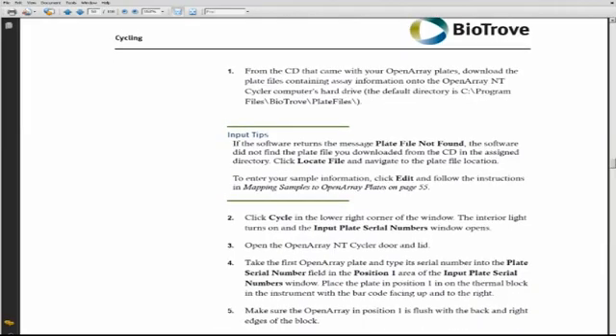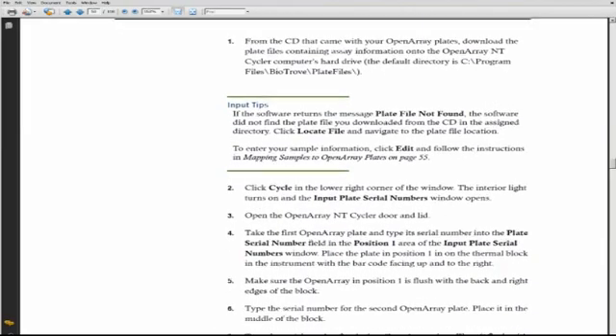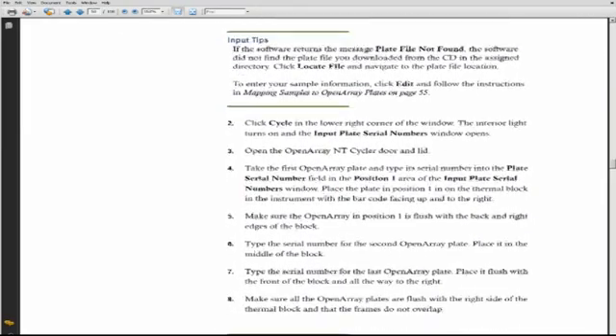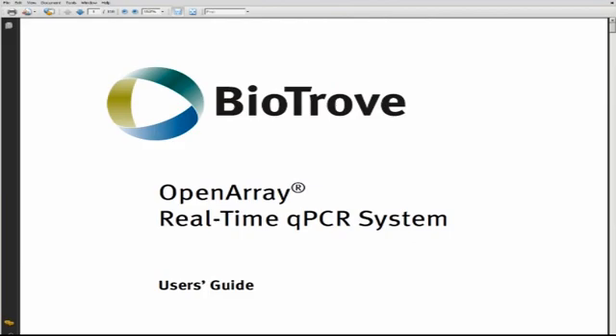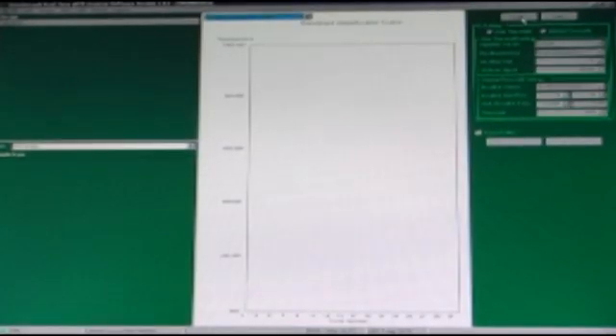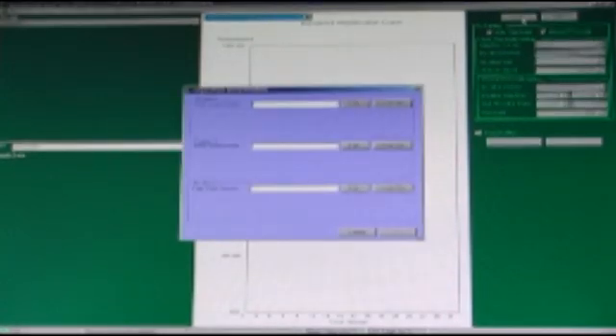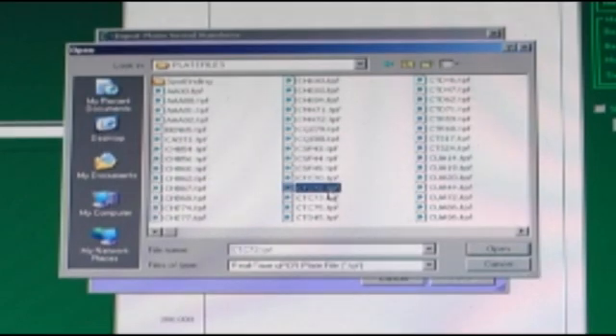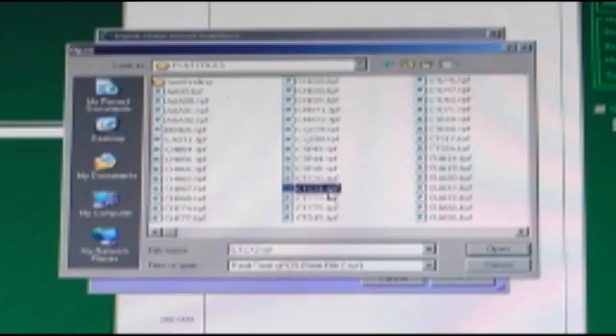I'll quickly run through the setup procedure for the OpenArray qPCR system, though the process is described in detail starting on page 51 of the user guide. With the disk that shipped with the OpenArray cards inserted into the disk drive, simply click on Cycle. Next, click on the Locate File button next to position number one and navigate to the appropriate drive. Select the .tpf file corresponding to the first plate you set inside the cycler and Open.